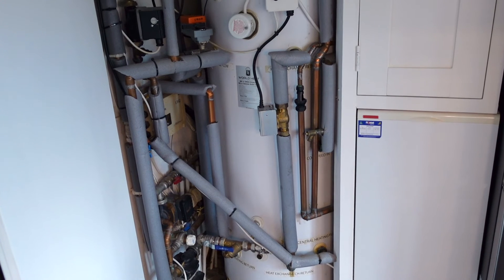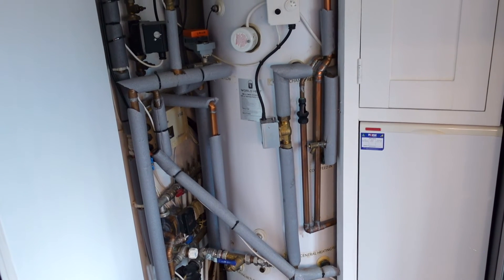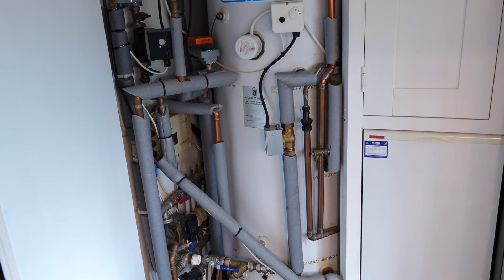As I've mentioned, in April we'll be diving into some serious modifications on our heat pump system, bypassing the buffer tank and removing all heating zones, which will hopefully create a far more efficient open loop system. Considering our current setup has already hit a COP of three this winter, I'm quite excited about the prospect of getting the system even more efficient. Our goal is a system that heats the whole house more effectively — especially the tricky TV room at the end — while using less electricity.